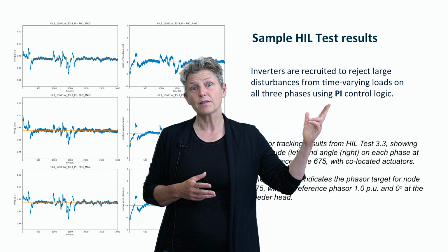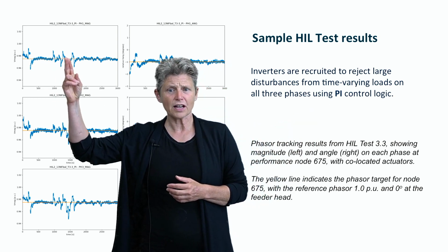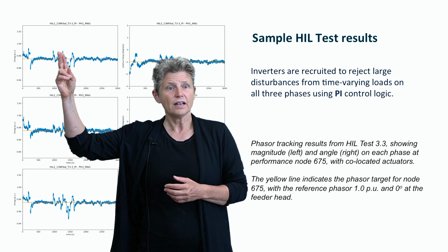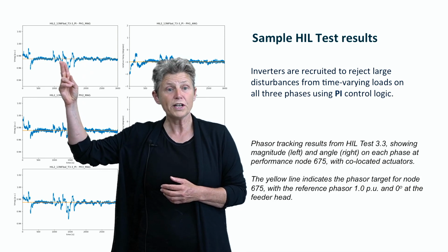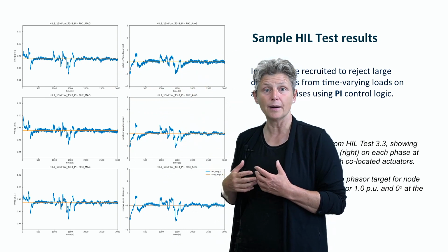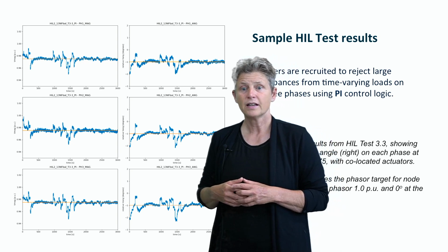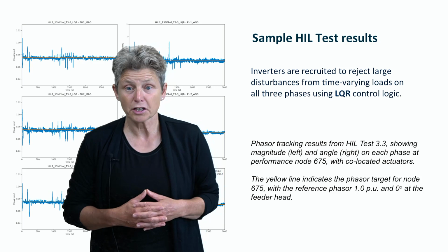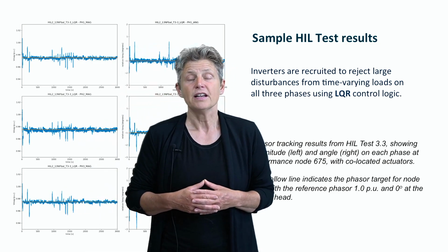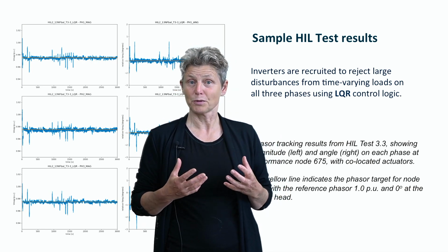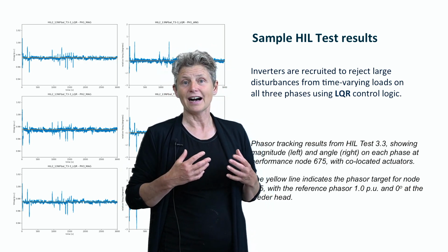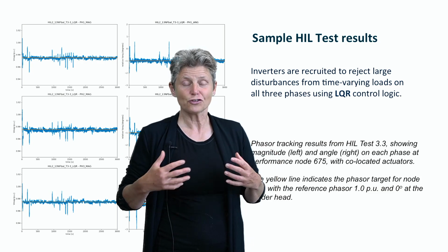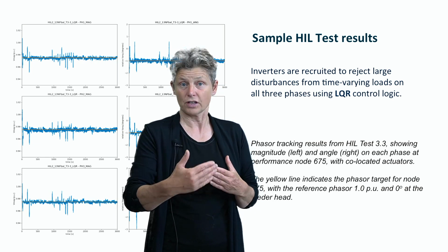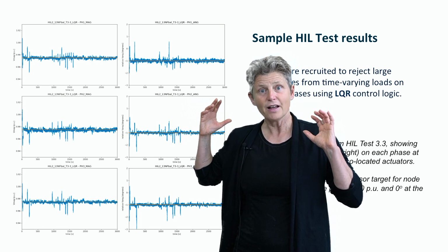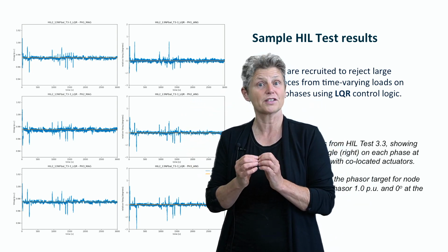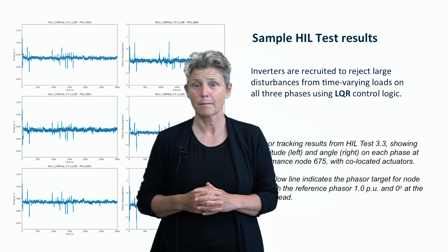And so what we're seeing here, using the proportional integral controller with a time step of, I think, half a second, it takes a couple of time steps to reject these disturbances, but we settle back on the desired target values. When we use the linear quadratic regulator, the MIMO controller, it goes much faster. And recall that this is the one that has the benefit of having a really good distribution circuit model. And so it already knows how much P and Q from the actuators it should need in order to achieve a certain change in voltage magnitude and angle. And so essentially within a single time step, that thing just drives the condition at the performance node back to the target. It's pretty spectacular performance.